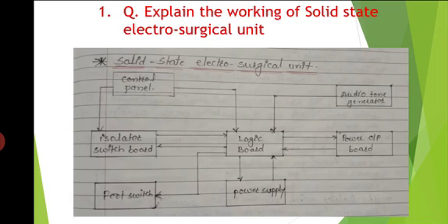The output of this high power push-pull amplifier is applied to a transformer, which provides voltage step up and isolation for the output signal of the machine. In order to facilitate identification of each mode of operation, audio tones with different frequencies are generated. So, a 1 kilohertz tone for the coagulation process, a 500 hertz tone for the cutting process, and a 250 hertz tone for hemostasis.